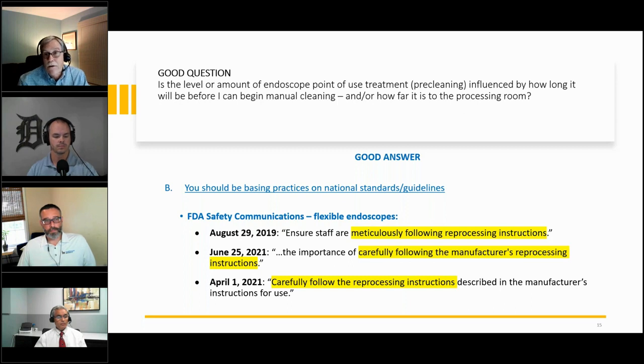feedback towards best practice. I've run into it a few times where people using more current generation Olympus scopes aren't using the air water channel cleaning adapter, what a lot of people refer to as the credit card, as per the IFU. They either don't know what it was for or they wrongly assumed it was an optional feature. But that's a required step that prevents, as it says in the IFU, clogging of the air water nozzle, and it can only occur when the endoscope's plugged into the processor in the procedure room.